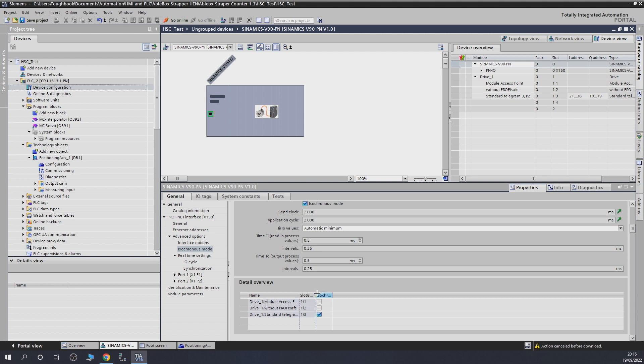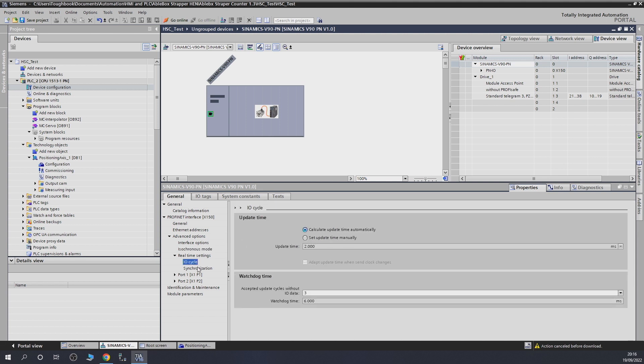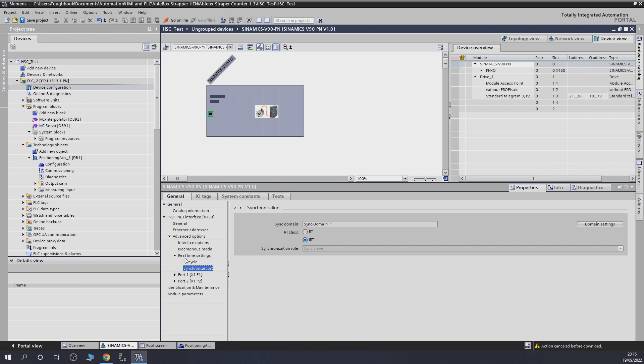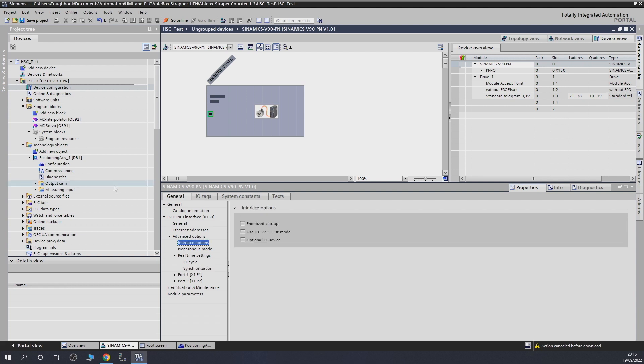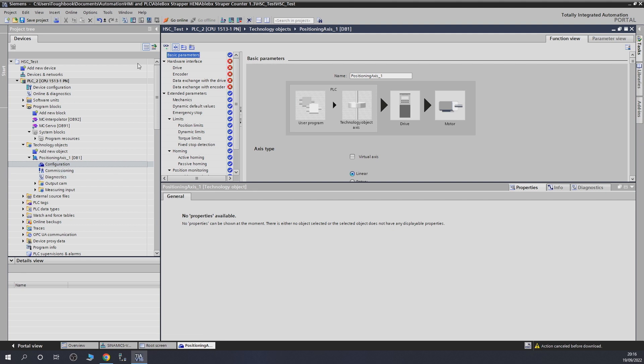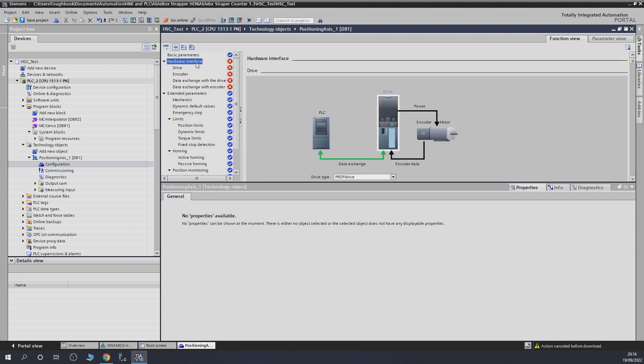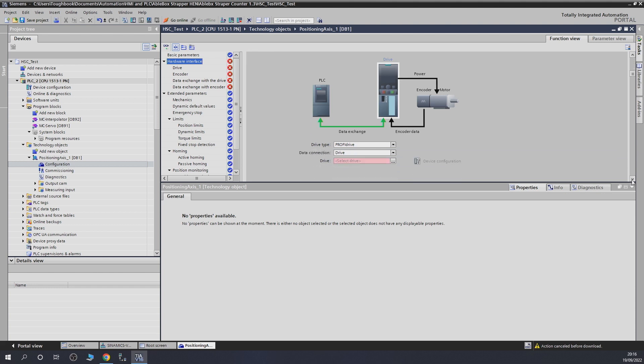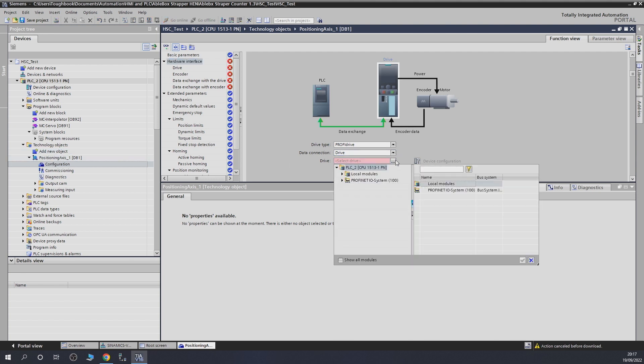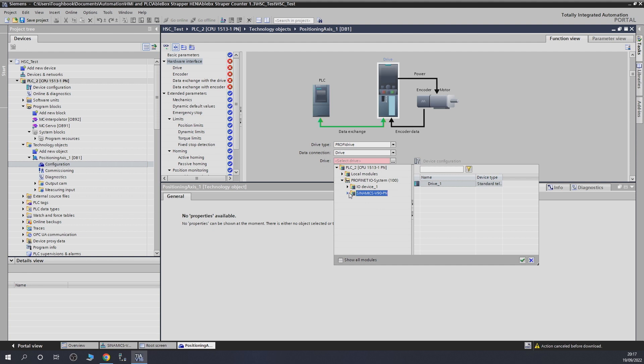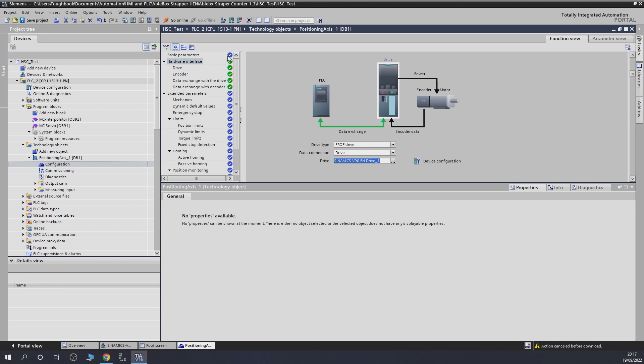If you want to read more detail about this, guys, do check out Siemens' videos. They are very good. So I've done that, that's all there, all changed as well. Once we've done that, we're going to go into configuration. We need to select a drive in here, which is this specific axis. If we have many axes, we would select it differently, but we want this position axis to this drive to be part of this. Select the three dots in here, go into Profinet IO system, select Sinamics V90. As you can see, it sits in there. For me, that name is wrong, but we're going to click OK. Once you've done that, everything gets green. It says now I know what I need to do.